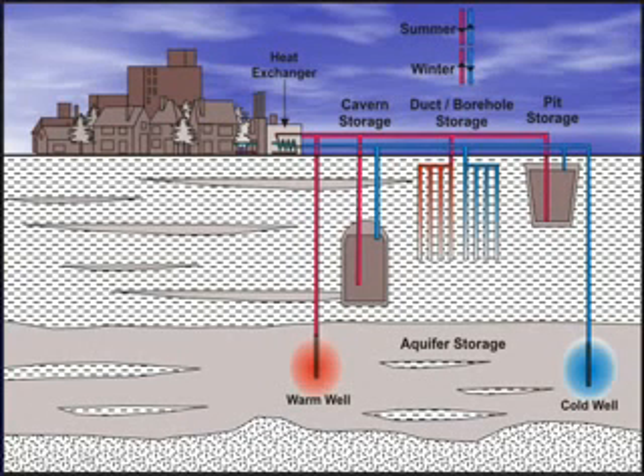During the winter season, we're taking this water and dumping heat into the building. So our groundwater is now colder because we've taken heat out of it, so what we're putting back in the ground is cold water. Then during the summertime, if we pump from this well, bring it up, put it across the heat exchanger, now we're taking heat from the building and dumping it into the water, raising the temperature of the groundwater, and we put it back into the aquifer to create a warm area. We can go back and forth on a seasonal basis.